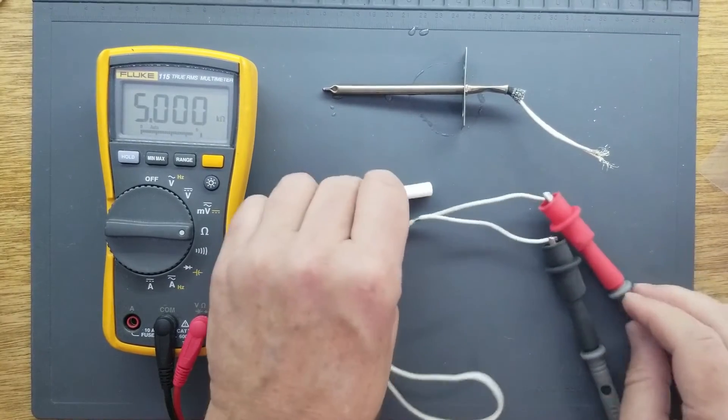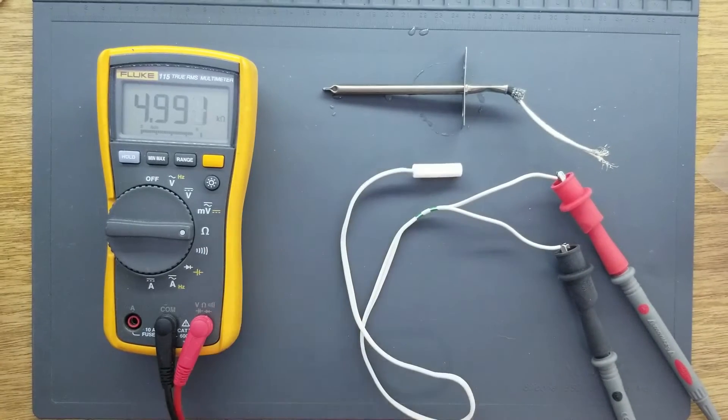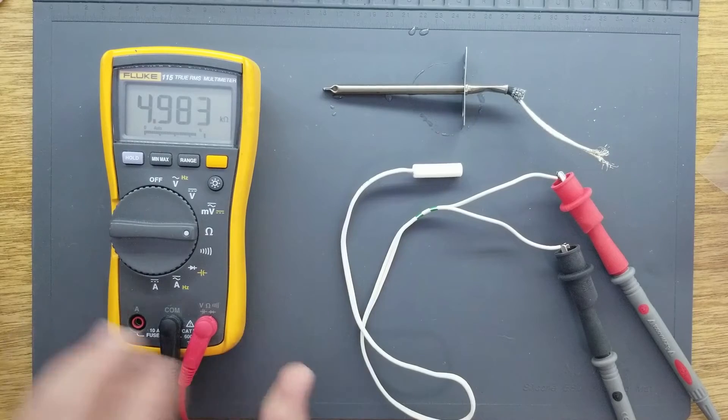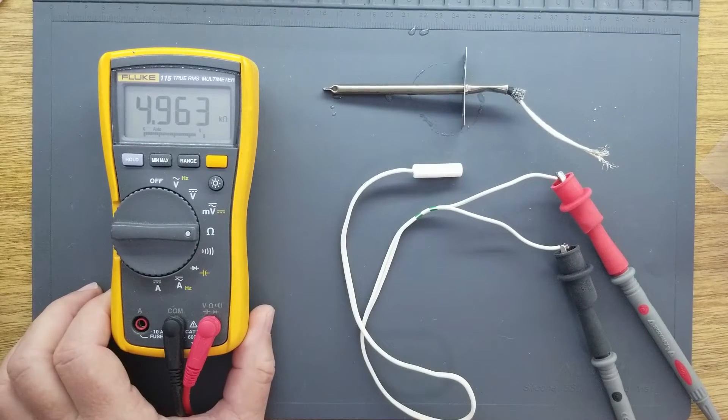This is a negative temperature coefficient thermistor, or NTC, out of a refrigerator. I've got it hooked up to an ohmmeter, and right now we've got 4.96 K.